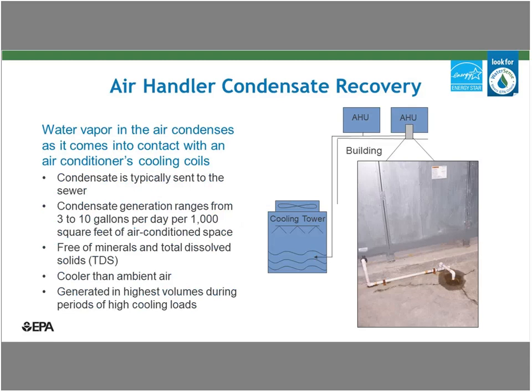So yes, as I mentioned, AC condensate can be an excellent source of makeup water, particularly if your facility is in a hot, humid climate. Air handler condensate is water that forms on the cooling coils as it cools and conditions outside air. Condensate is typically drained to the sewer or sometimes the storm sewer, but since it is generated in highest quantities when the load of your cooling tower is at its greatest, it makes a really excellent source of cold, clean water to feed to your cooling tower.